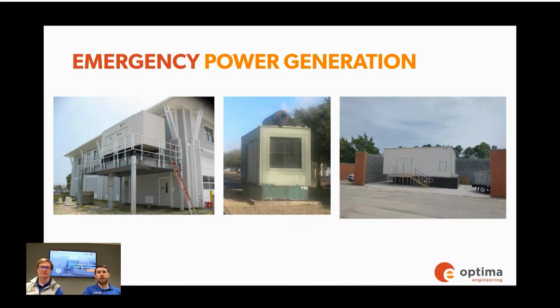Keeping cost in mind, natural gas generators are typically more expensive than diesel. Another thing to consider is the location on site. Keeping in mind your project is at the coast, you might want to consider locating your generator on a platform, like the image on the left side of the screen, or you could locate the equipment on the roof.